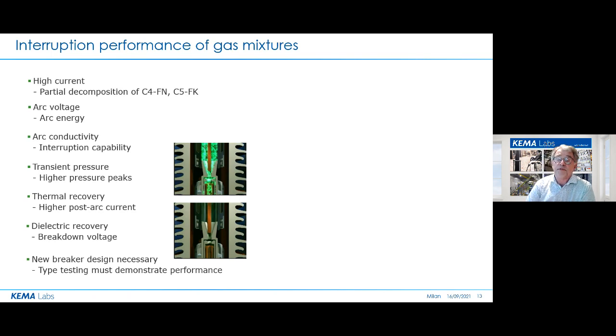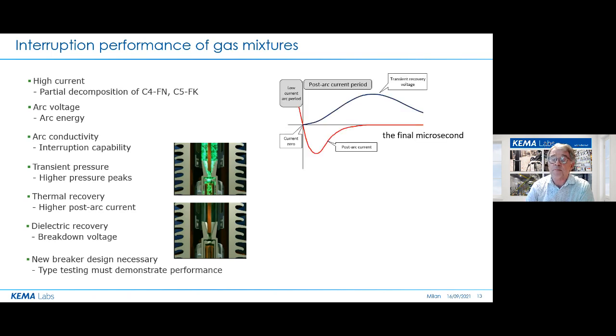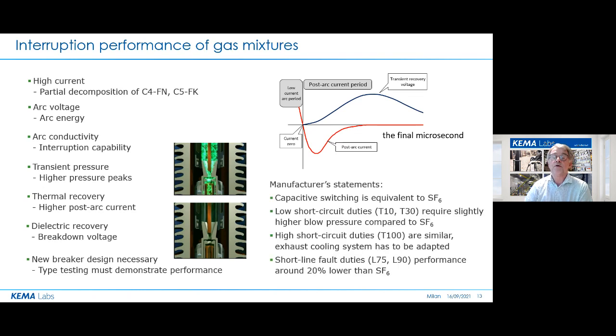Fault current interruption is a delicate process that is basically determined in the last few microseconds before interruption, where the remaining arc plasma needs to be removed from the switching gap. Designers have mastered this process also in the new designs, which means that if you compare the interruption of the new gases with SF6, it is stated that the capacitive switching is equivalent to SF6.